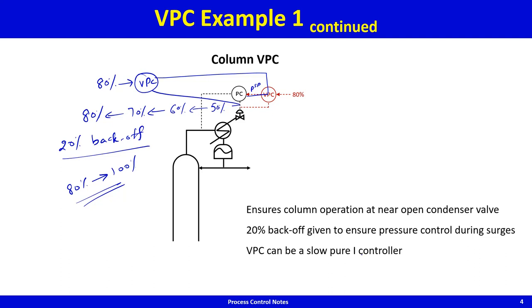Note that the valve positioning controller can be a slow controller — it could be a pure integral (I-only) controller. Because the column pressure is floating, this is also called floating pressure control.